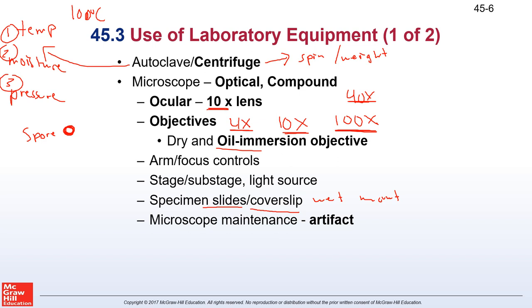If you don't handle your microscope appropriately, don't clean it or provide maintenance, you may damage it, cause scratches, or contaminate it. Inside the ocular, you might get dust and particles, and as much as you want to wipe the outside, you'll never clean the inside. So it'll show up and might look like a specimen, but if you change the slide, it's still there. If you change the objective power, it's still there. So it's not the actual specimen, it's some mark that's inherent to the microscope.